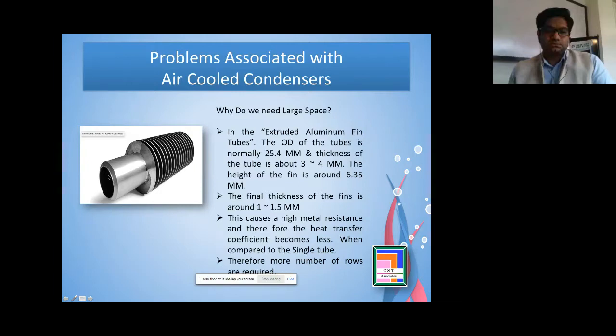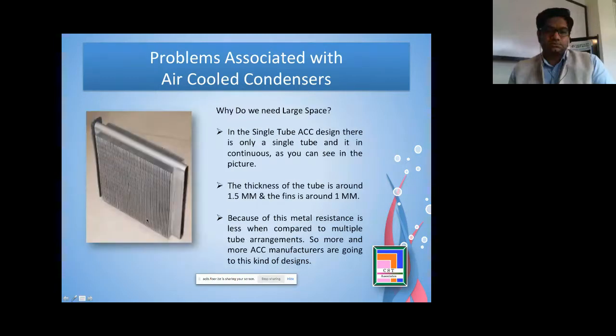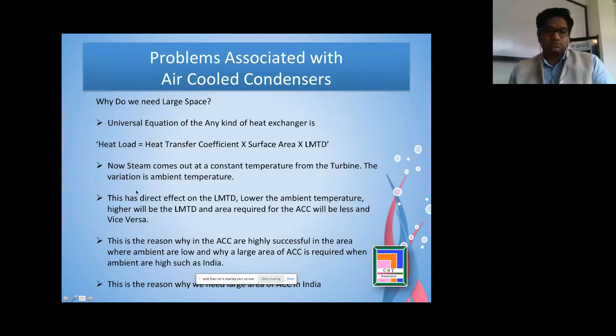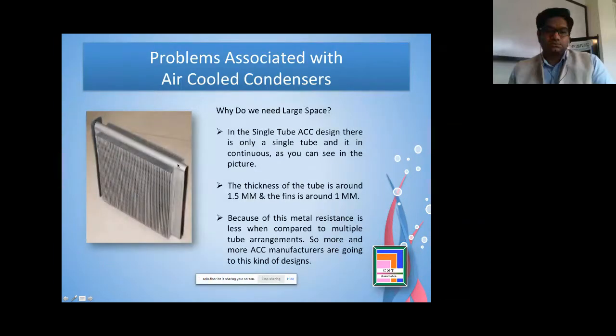To overcome the metal resistance, the single tube concept was introduced. So this is the one. This is a single tube, and the air blows from here to here, and the steam goes from this side to another side. The thickness of the tube is kept at 1 to 1.5 millimeter, and this is rolled. It is an aluminum coated sheet, and both the aluminum fins and the tubes are kept in a furnace, and then the aluminum inside the furnace melts with the brazing material over here, and this becomes an integral part.